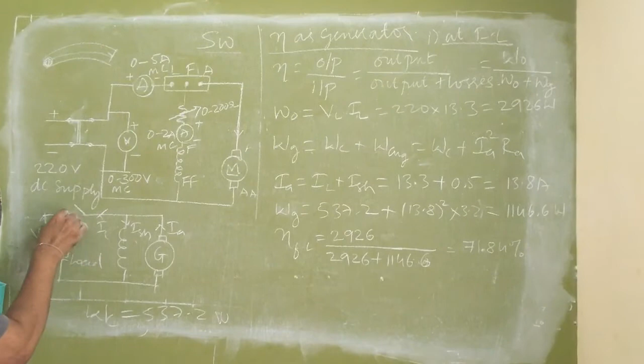Why? Because now if I disconnect the load for the generator, my IL becomes 0. Don't worry about IA, worry about IL. If I disconnect the load, my IL becomes 0. The moment IL becomes 0, it is a no load current. If the load is maximum rated, IL becomes rated current, 13.3 amperes. If the load is 50% of rated, IL becomes 13.3 into 50%. So this concept is used in case of generators and transformers, but not motors.